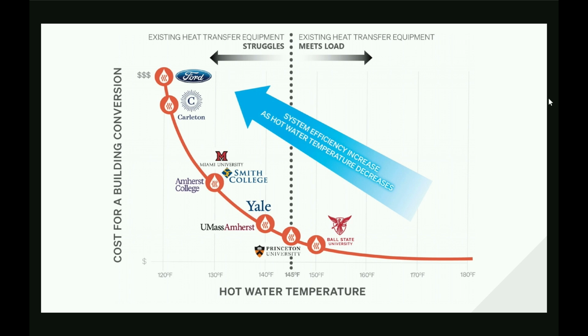So how do you come up with the optimum water temperature without spending major money converting your buildings? What we started 15 years ago at Ball State was the easiest thing: reset the water temperature back and see how far you can go before everything blows up. We could do it theoretically, spending a lot of time looking at coils and running load calcs, but this approach tells you exactly what the water temperature should be.